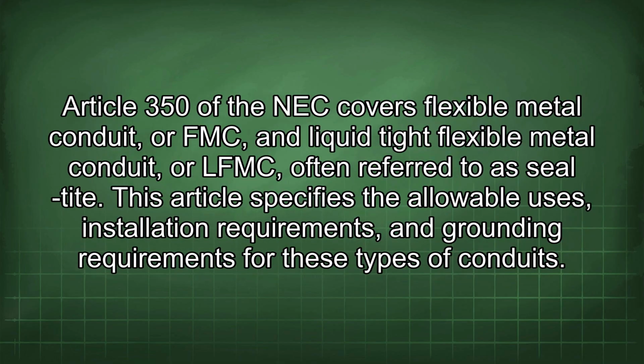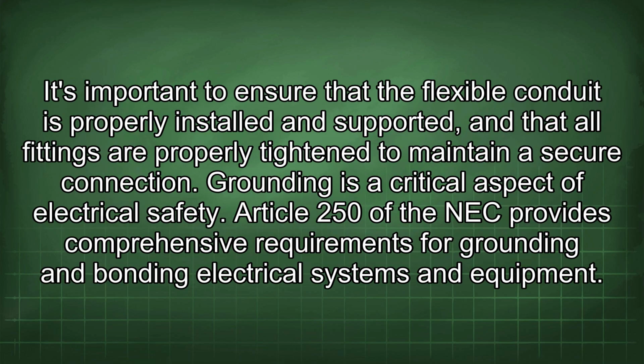Article 350 of the NEC covers flexible metal conduit, or FMC, and liquid-tight flexible metal conduit, or LFMC, often referred to as Seal-Tite. This article specifies the allowable uses, installation requirements, and grounding requirements for these types of conduits. It's important to ensure that the flexible conduit is properly installed and supported, and that all fittings are properly tightened to maintain a secure connection.